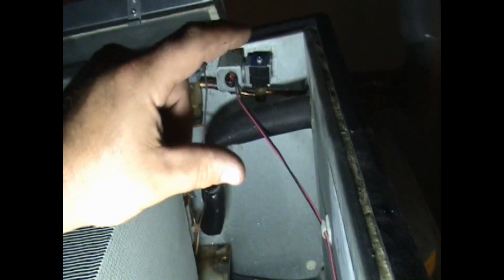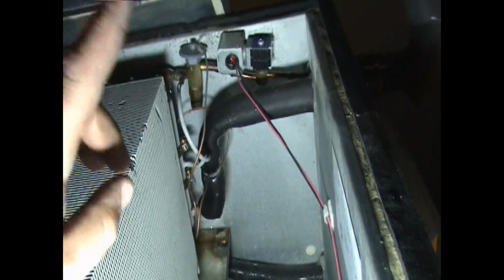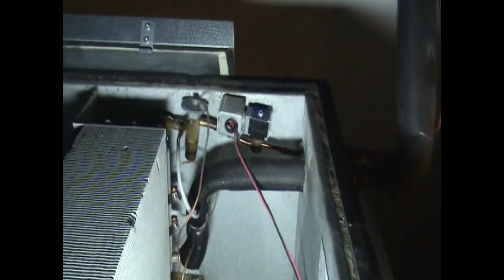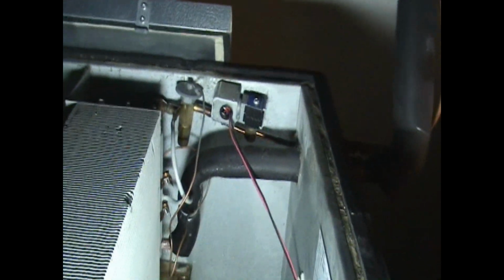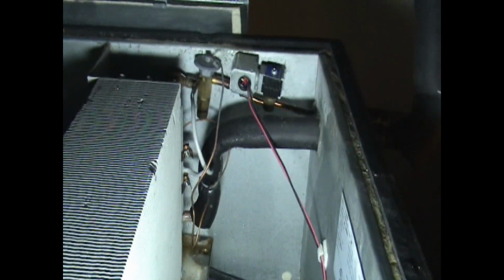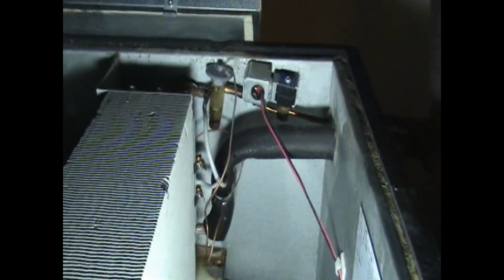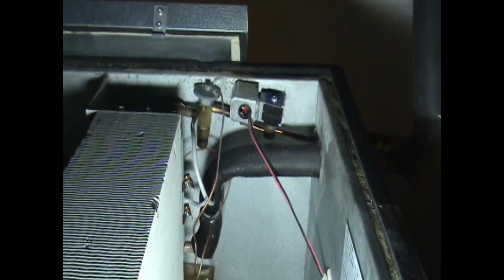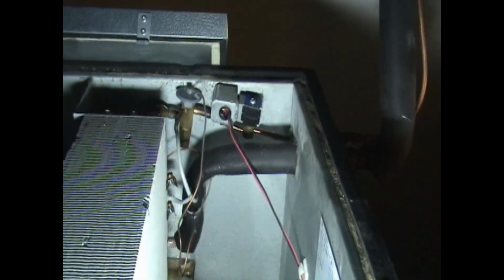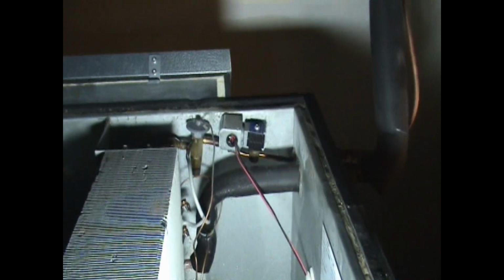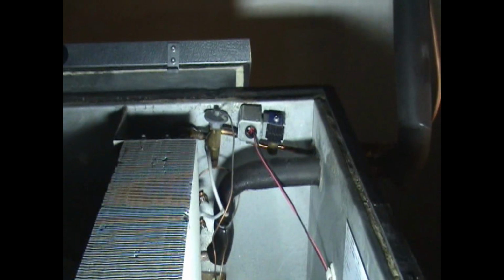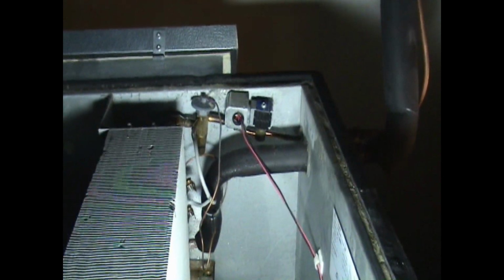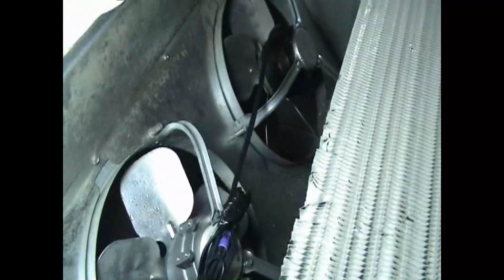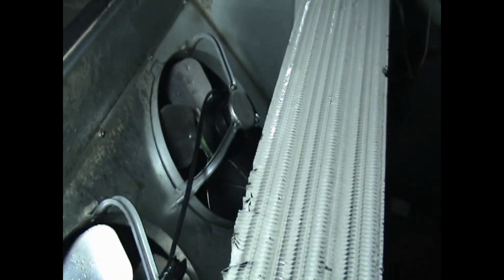When this is satisfied, it closes that valve, which is basically just like a gate valve, only electronically operated. It closes, stops the flow of refrigerant to this, while the unit on the roof is still running. It causes the unit to pull all the gas that's in here back up to the roof, and it causes a low pressure situation. The low side pressure will go down, and when it goes down to a certain point, there's a control on the roof that'll shut the unit on the roof off. That's pretty much how these work and maintain temperature. So let me get back out of here and start her up.